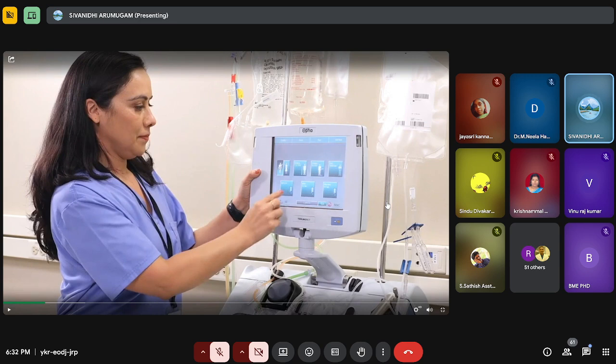See, the first important thing is who the giver is. For example, if the giver is a donor, not a patient, then we need to configure their vital details. Here we need to mention gender, male or female, then height, weight, the HCT value, and the flow rate that we need to set. The operator will configure these donor vital details before donating blood. Then the calculation will happen.